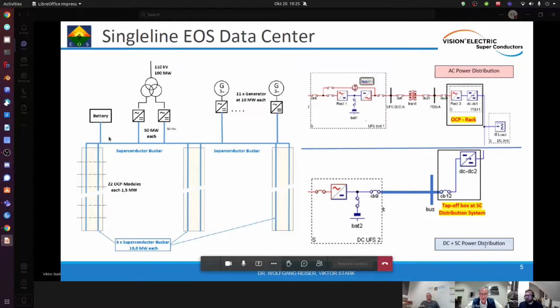The nice part is we are here working on a voltage of the battery level. That means we do not need battery for emergency cases in each of those modules, but we have moved the battery outside. There is no resistance between battery and the single OCP modules. That means there is no voltage drop in between, there is no power loss in between. So the battery works as if the battery is directly standing beneath a module or beneath a server rack.